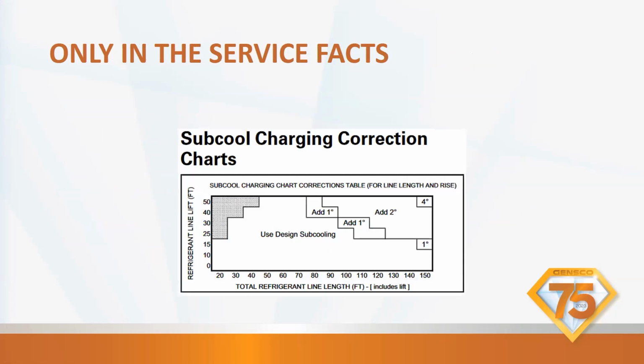Okay. In the service facts, there's subcooling charge correction charts. So when you're looking at the subcooling on the outdoor unit, depending on the total line length and the lift of your refrigerant line, you may need to add subcooling to that number on the outdoor unit. Okay. So if you look at those where it says design subcooling, use the design subcooling.